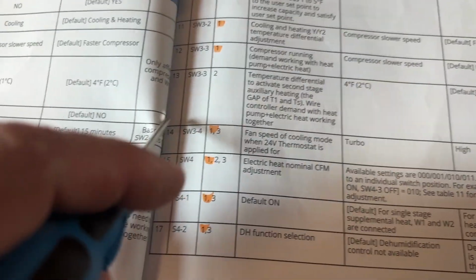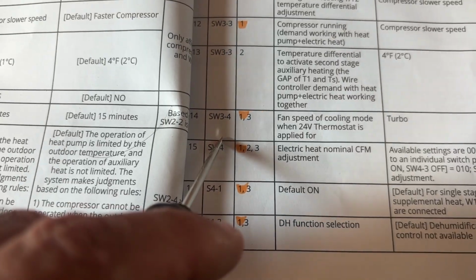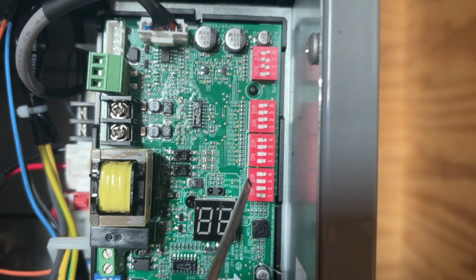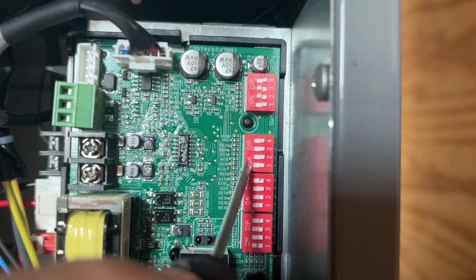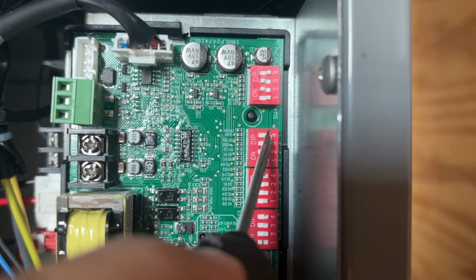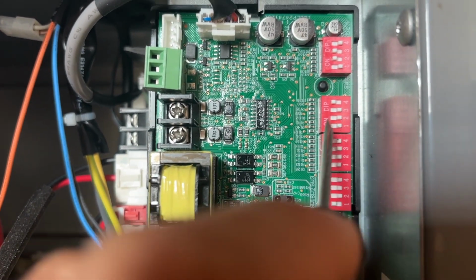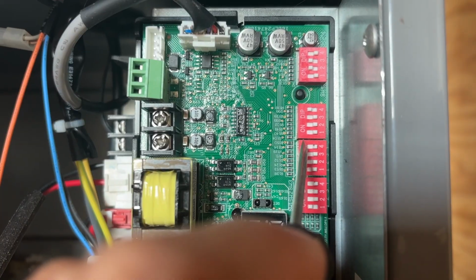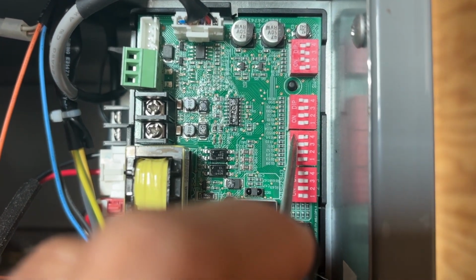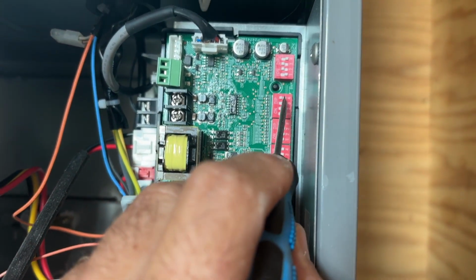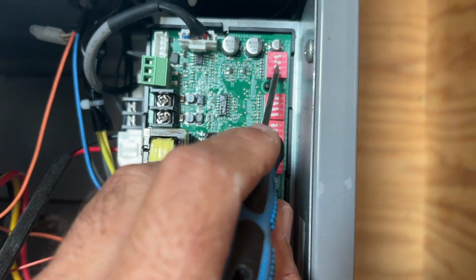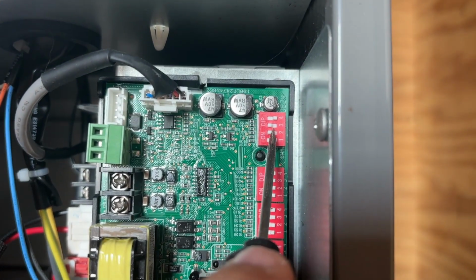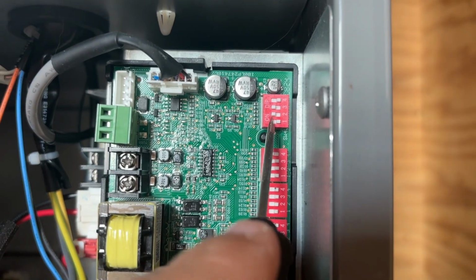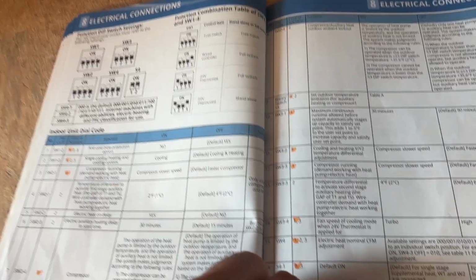So again, that is SW34. Let's go ahead and turn that on. 1, 2, 3. The 4th switch, 1, 2, 3, 4. It's going to be this one. We have that switched on. Also, by the way, you want your power off when you're moving these dip switches, so completely power the unit down. So we're all set there with those, and then we have our last SW4 switch with 1, 2, 3, and 4 here, and this is based on your auxiliary heat model.